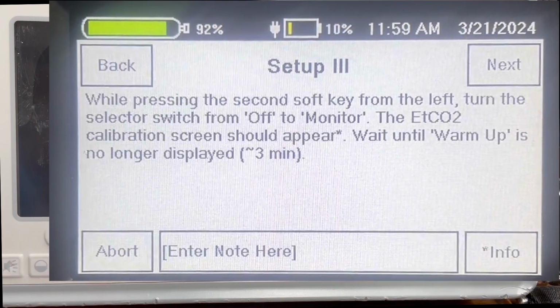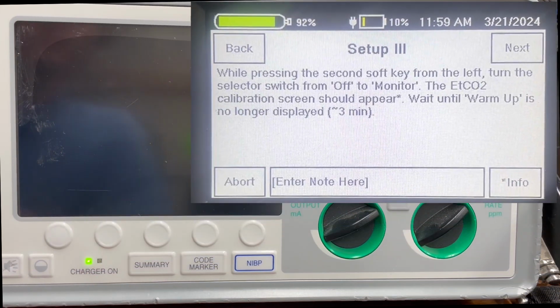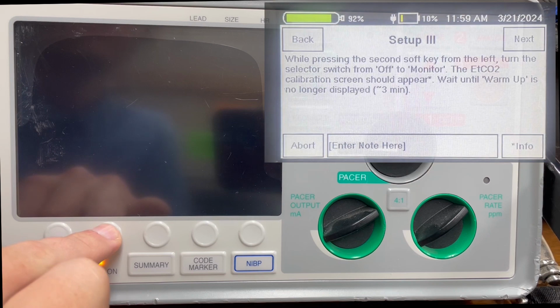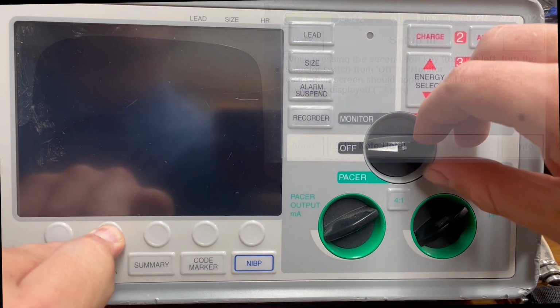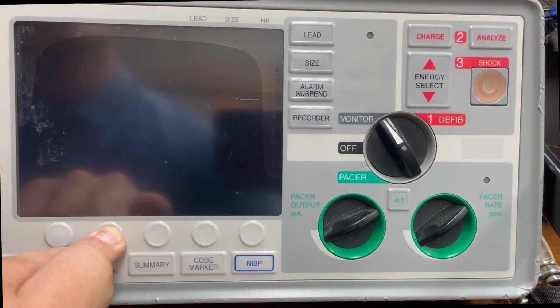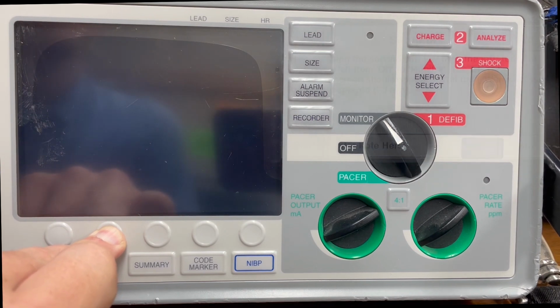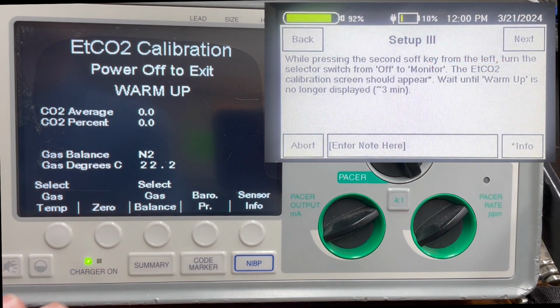Setup 3 is actually going to be turning on the defibrillator. To do this, we hold the second from the left soft key down while turning our switch from off to monitor. We'll give that a few seconds. Going to bring us to our end tidal CO2 calibration screen. The Smart Tank is wanting us to wait till it's flashing warm up stops flashing. It usually takes around 2 to 3 minutes.